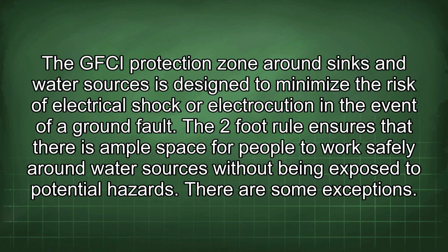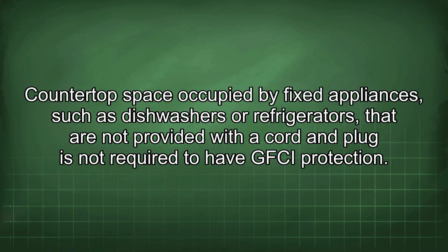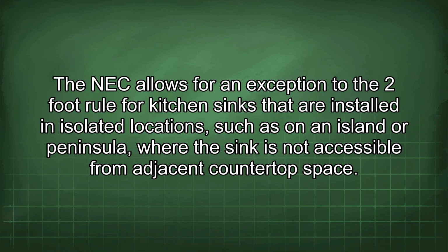The 2-foot rule ensures that there is ample space for people to work safely around water sources without being exposed to potential hazards. There are some exceptions. Countertop space occupied by fixed appliances such as dishwashers or refrigerators that are not provided with a cord and plug is not required to have GFCI protection. The NEC allows for an exception to the 2-foot rule for kitchen sinks that are installed in isolated locations, such as on an island or peninsula, where the sink is not accessible from adjacent countertop space.